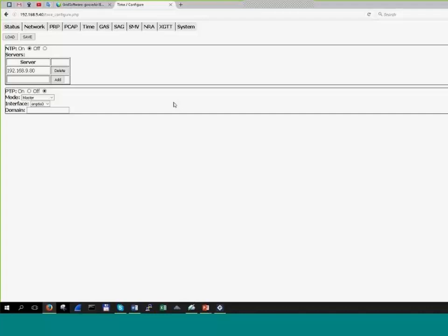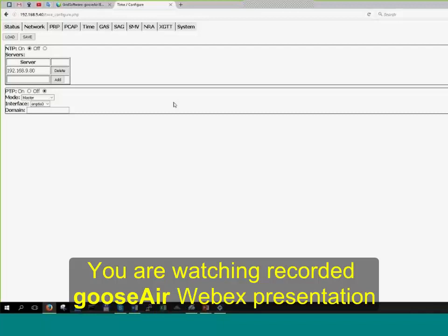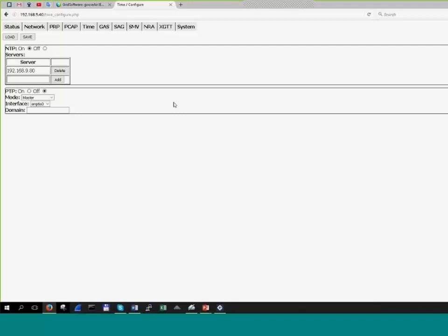And at the bottom you have PTP options, so you can synchronize gooseAir with any PTP clock, or you can add an additional card on the gooseAir PC and get the GPS signal and act as a master. So you have options to add additional cards. Is it a specific card? It is different cards. One is pulse per second, that's to allow sample values to be synchronized, and there is also a variety of other cards that you can get, with an antenna, to get the GPS and the clock, basically. Okay, so the hardware is capable of handling these cards mechanically? Yes. It's a PCIe 4 interface.